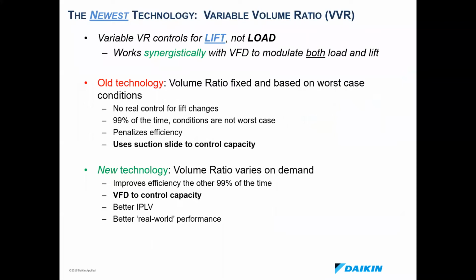So essentially, the old way modulation was done was that there was a slide valve on the suction side of the compressor, which would control for capacity. And it would not be able to control for lift. It would only be able to control for the capacity.